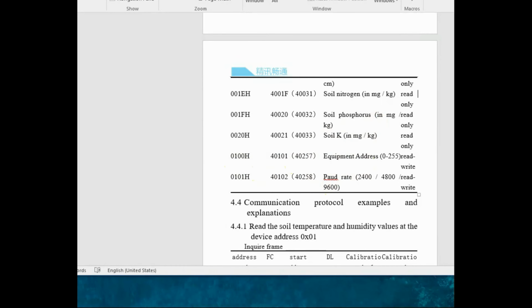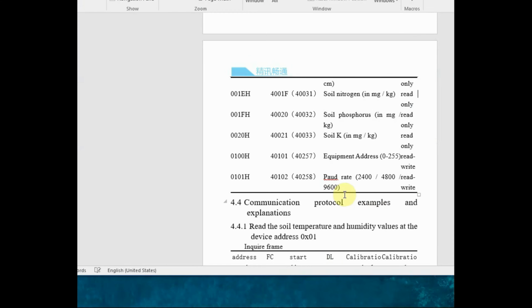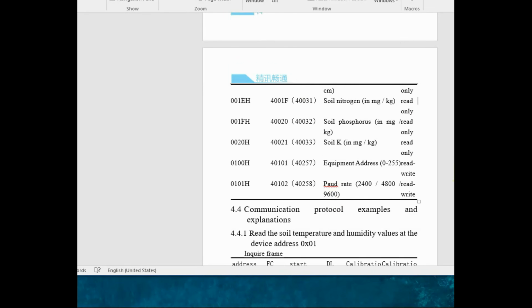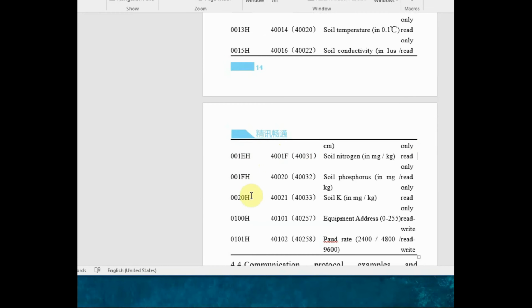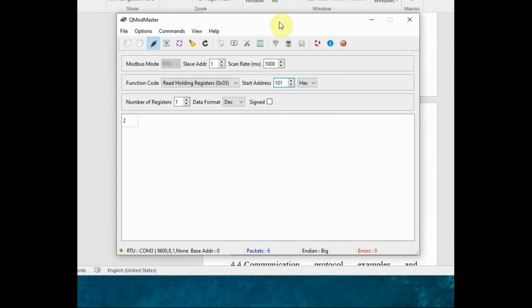Now let us see after feeding 0100 and reading that register. Click on command read write. It gives the value 1, which means the slave address of that NPK sensor is 1. You can also write the holding registers to change this value. And for the baud rate you have to feed in 0101. You get 2, which is 9600. So 0 means 2400, 1 means 4800, and 2 means 9600 baud. The slave address and baud rate you can change using the write holding registers.